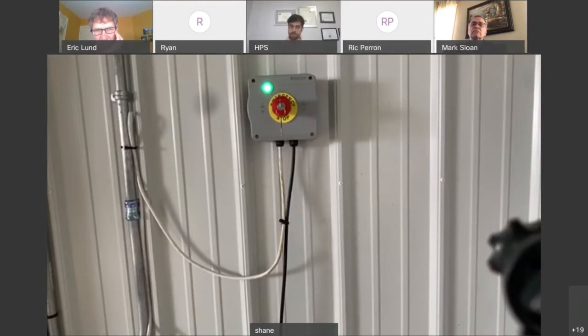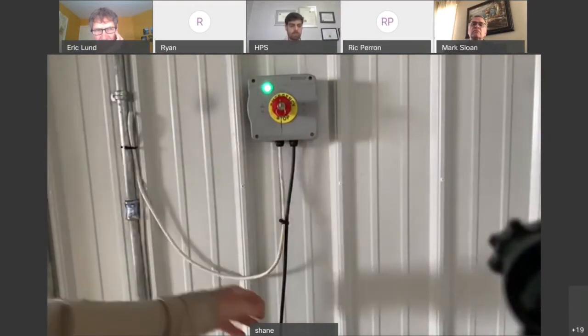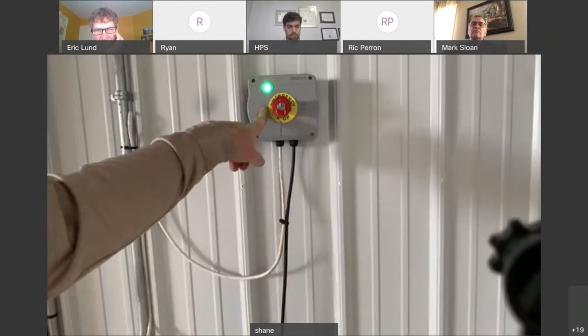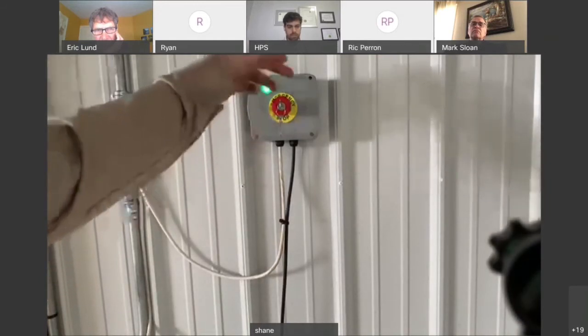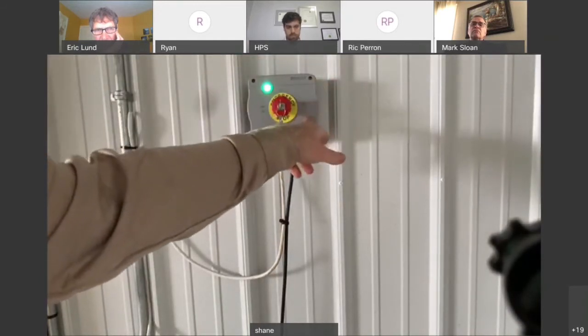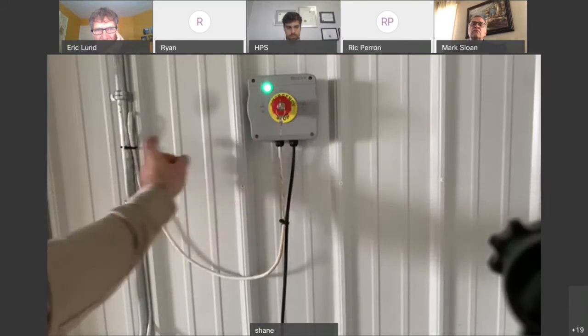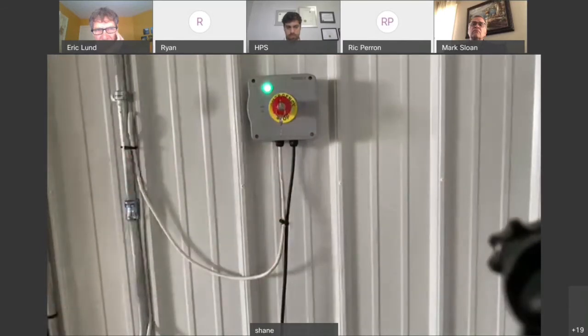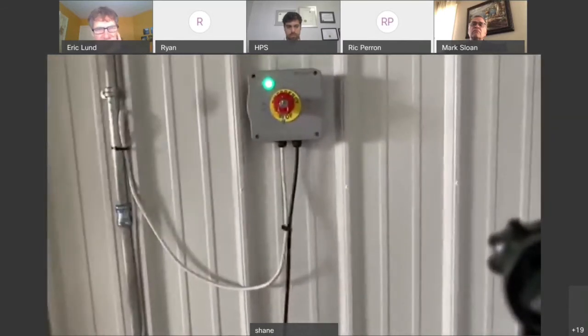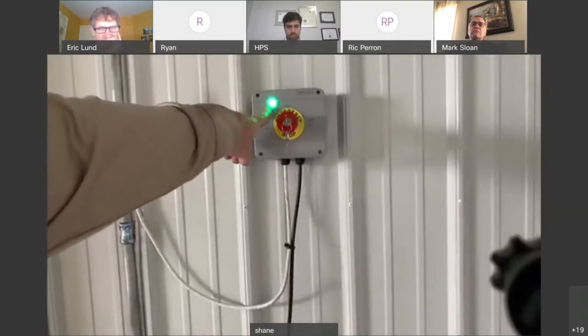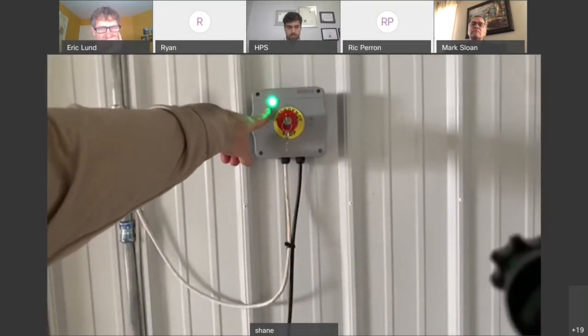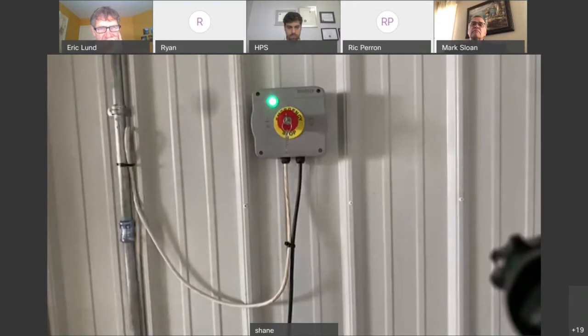But you also bring down your 24 volt supply wire to the initiator, which also has your 24 volt power supply from a step down converter from a 120. You can see here, what this is telling me right now is that there is input coming from the grid, because that's what we're worried about. If we lose the grid, we need this to shut off, so when the firemen show up, they can chop through the roof and have no issues.